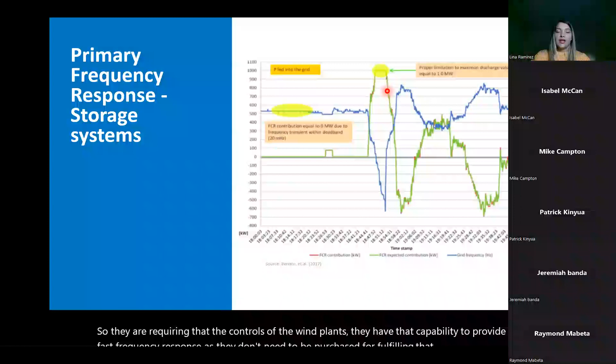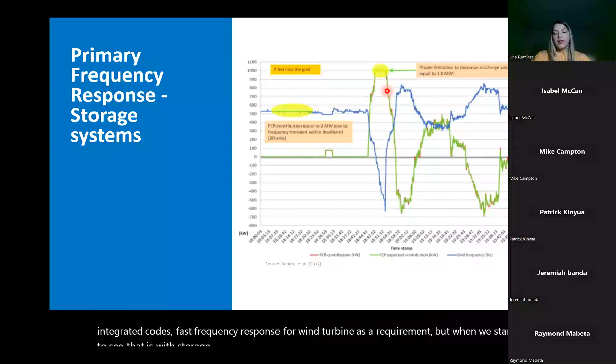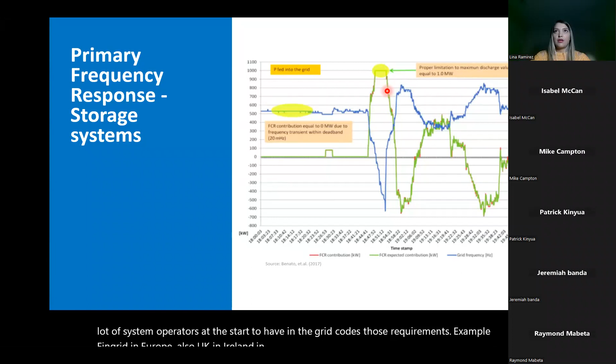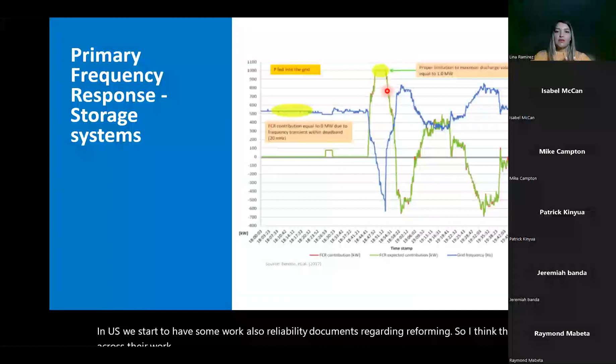Also Brazil and Colombia have fast frequency response for wind turbines as a grid code requirement. But when we see it with storage, say PV plus storage or storage alone, it's usually through the market. Going further into pure technologies, grid forming is also providing those capabilities, and usually grid forming can be achieved with storage. We have a lot of system operators starting to include those requirements in grid codes - examples are Fingrid in Europe, also UK, Ireland, AEMO, and in the US we have NREL reliability documents regarding grid forming.